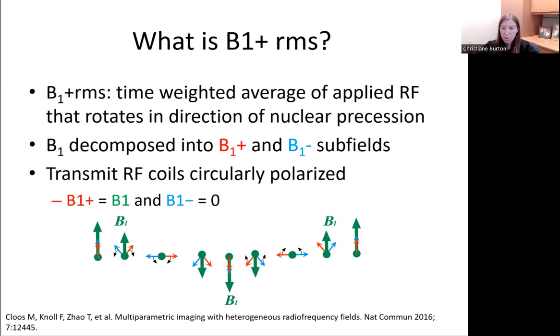In brief, the sinusoidal fluctuation of the transmit RF field, B1, the green arrow, can be decomposed into two components, each half as large. A component rotating in the same direction as the nuclear precession, B1+, and a component rotating in the opposite direction, B1-. The B1+ subfield is responsible for tipping the nuclear magnetization. The B1- subfield rotates opposite to the spin system, generating only heat via induced electrical currents, but having no effect on nuclei.